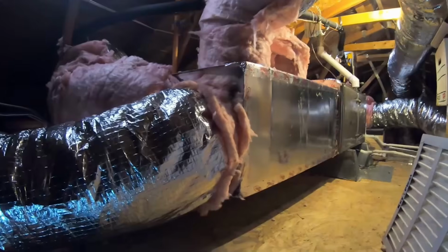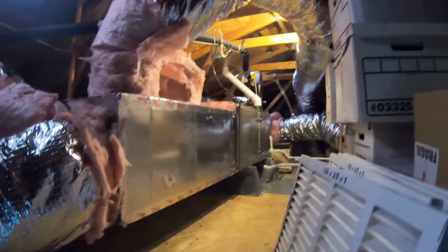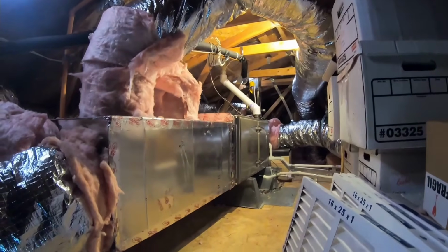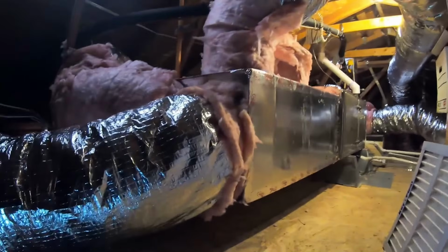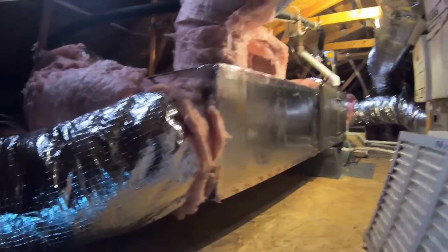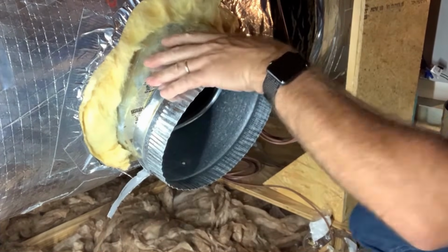Not enough return air vents. A typical forced air HVAC system is designed the same way as a closed-loop system. In a perfect world, it produces a certain amount of air, and that air is distributed throughout the home, so the same amount of air is returned from the home, conditioned, and then redistributed. Each area that is receiving a measured amount of air should also be able to return the same amount of air to the system.